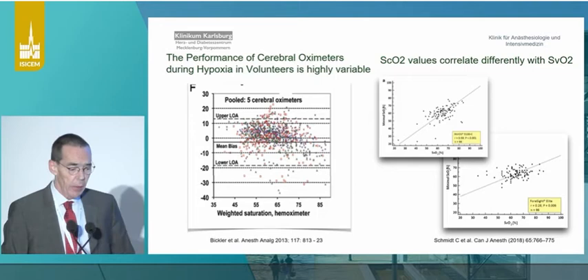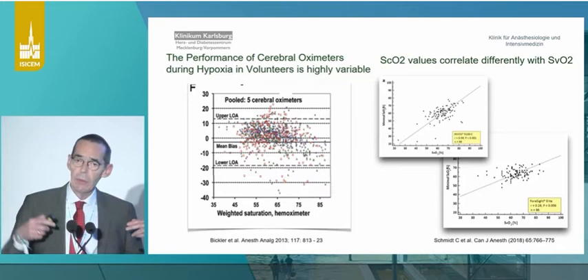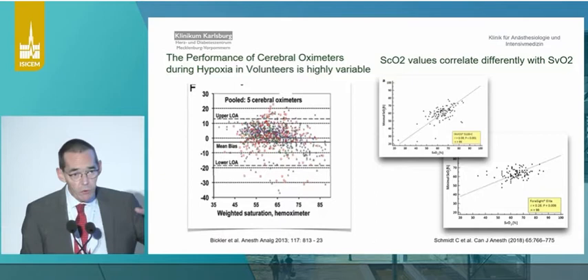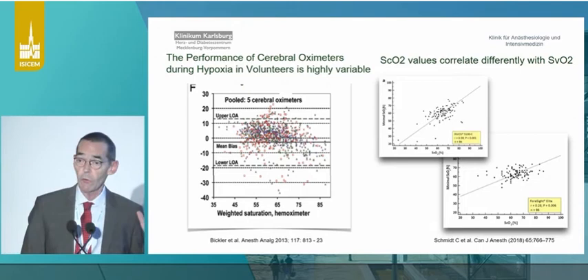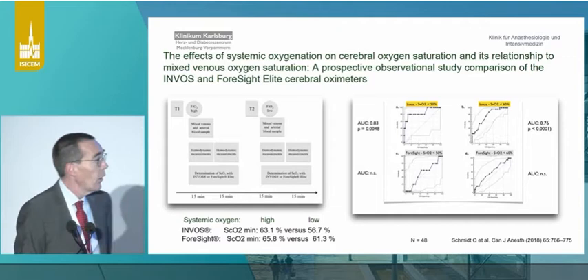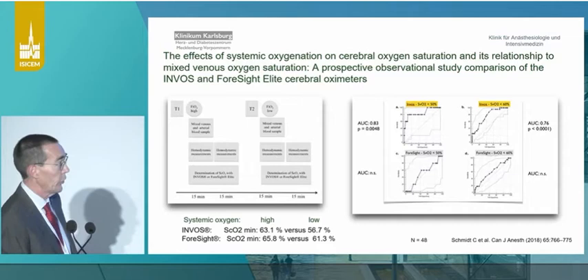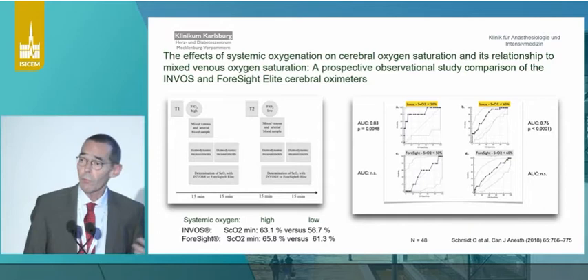This is really important information. If you compare different cerebral oximeters — as has been done by Phil Bickler, one of the people who calibrates these devices for the industry — there is an extreme variability in the numbers, and you cannot translate information you get with one device to information from another. This may have clinical implications. For example, looking at the relationship between cerebral and mixed venous oxygen saturation, we found a clear significant difference in the correlation between mixed and cerebral oxygen saturation readings with different devices. One device is capable of showing that mixed venous saturation is below 50 or 60 percent — meaning in a critical range — while the other is not.